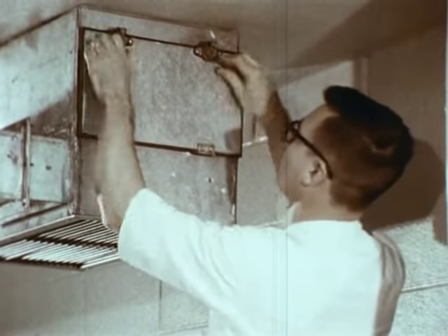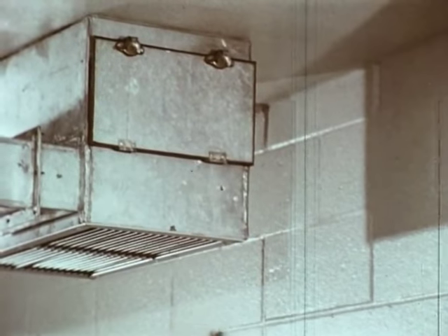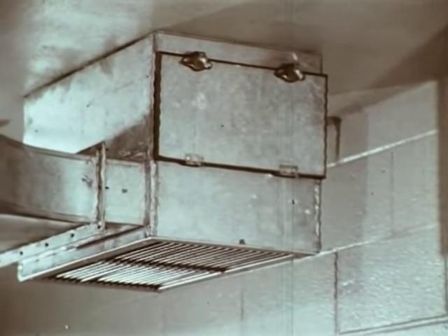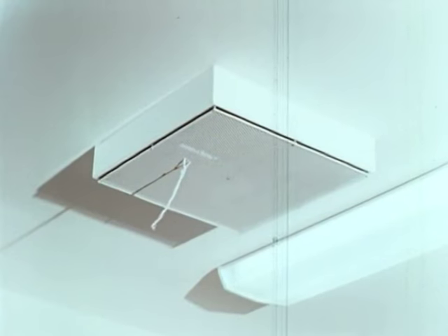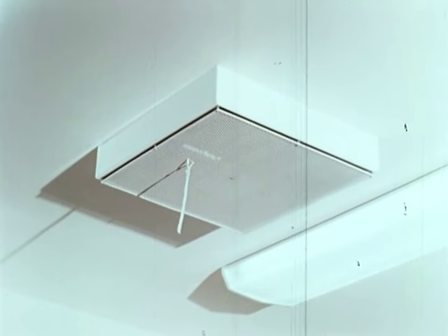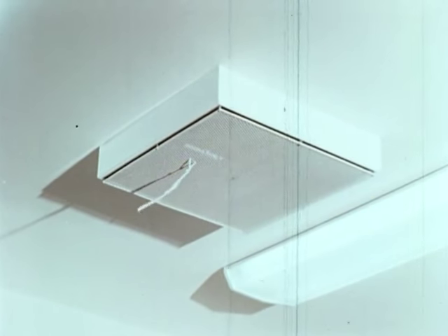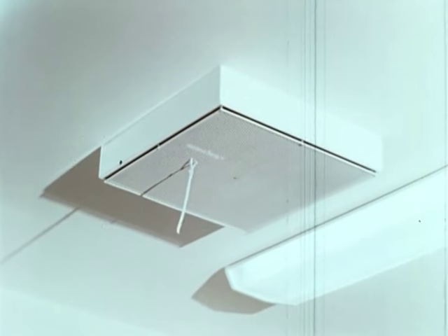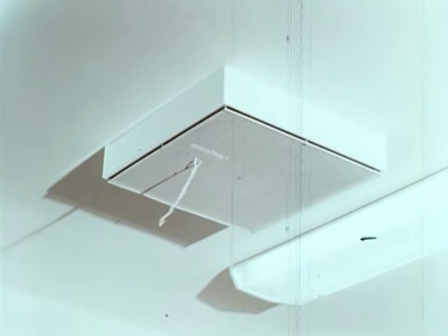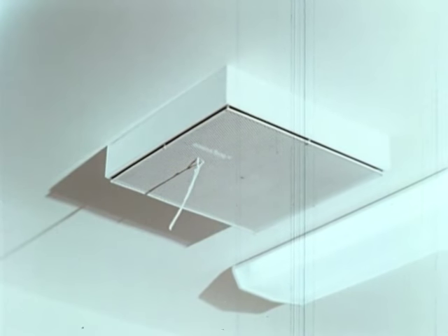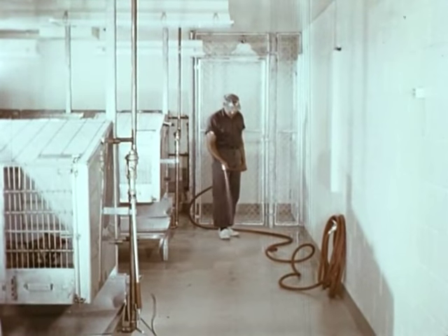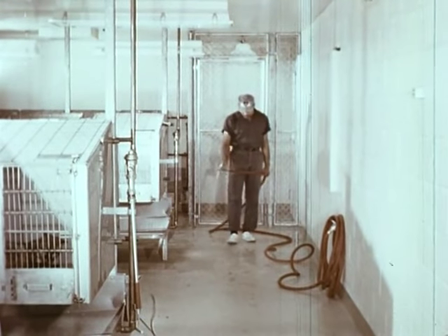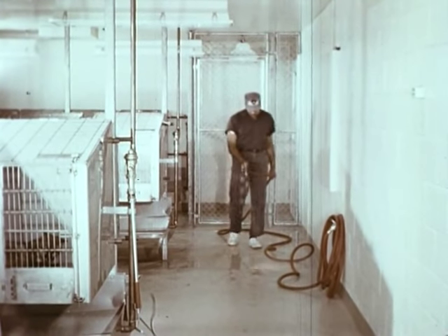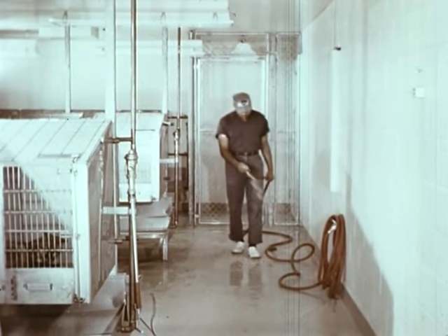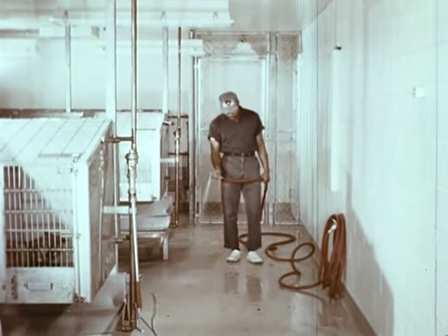In the animal rooms, dust filters should be installed in the air exhaust ducts to prevent excessive loading of the downstream microbial filters with animal hair and dander. The recommended ventilation rate for the rooms is 15 changes per hour of non-recirculated draft-free air of the relative humidity and temperature appropriate to the animal species. Since the walls and floors of both large and small animal areas are washed frequently and exposed to urine and other wastes, careful selection should be made of wall paints and finishes.